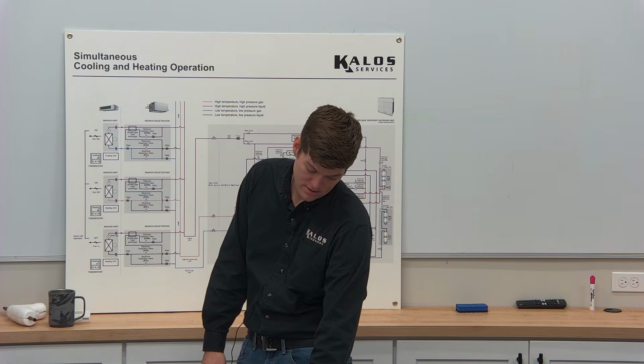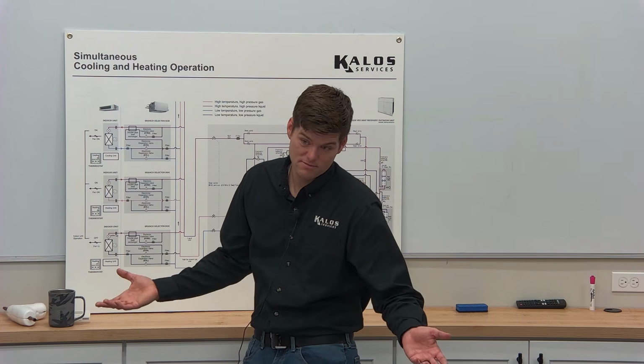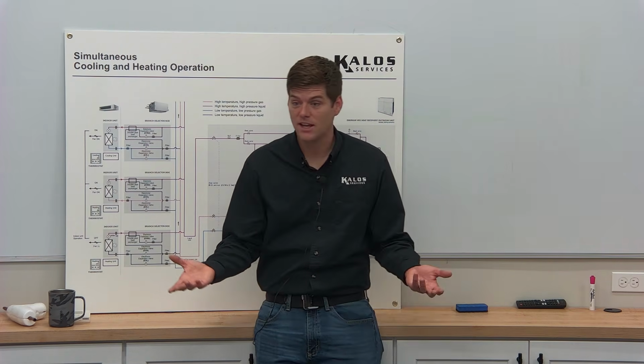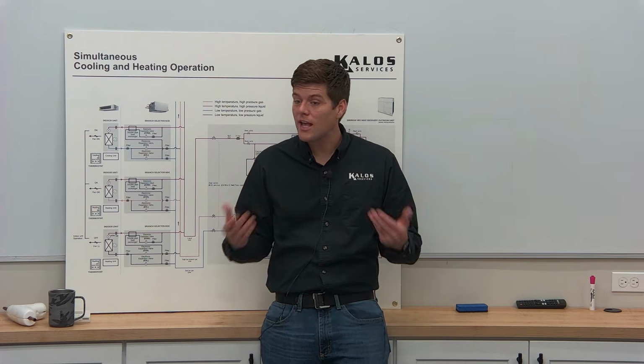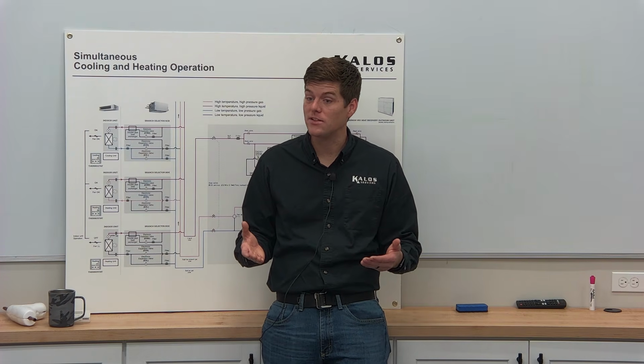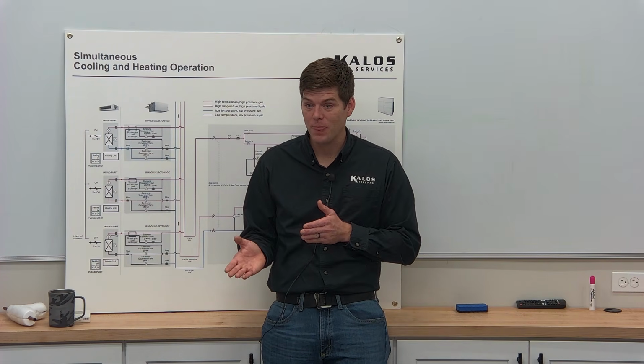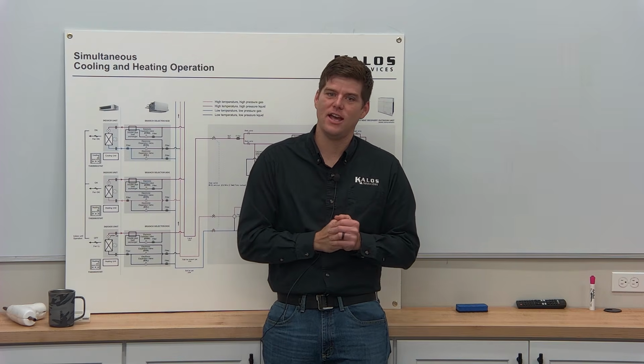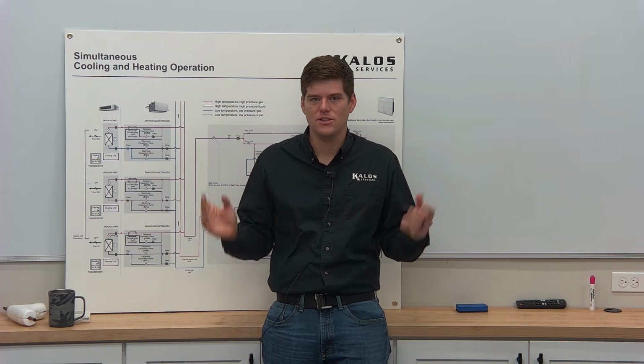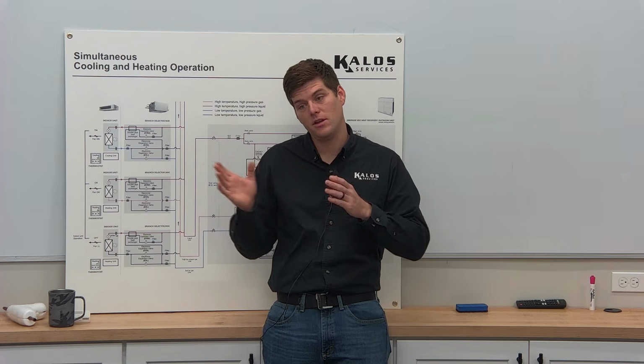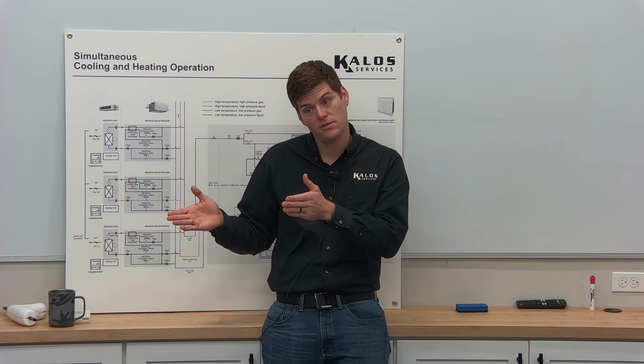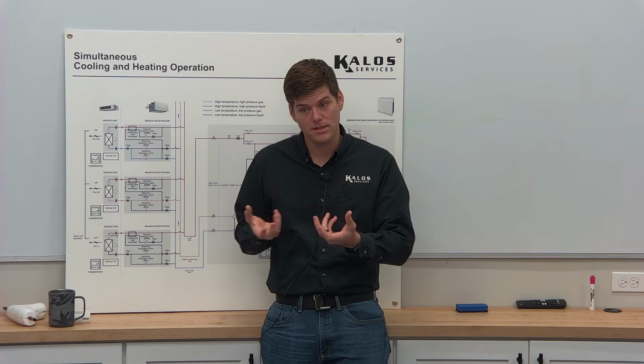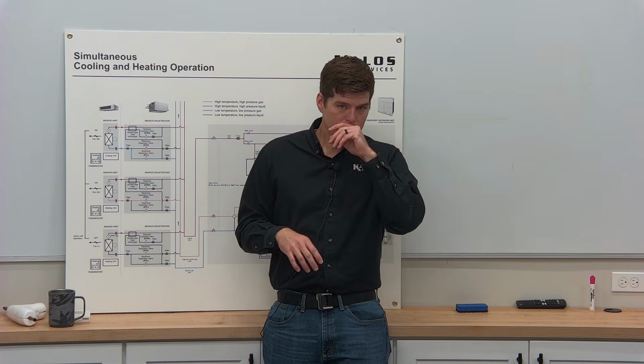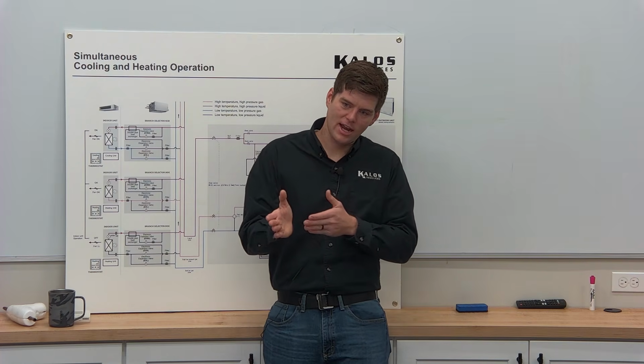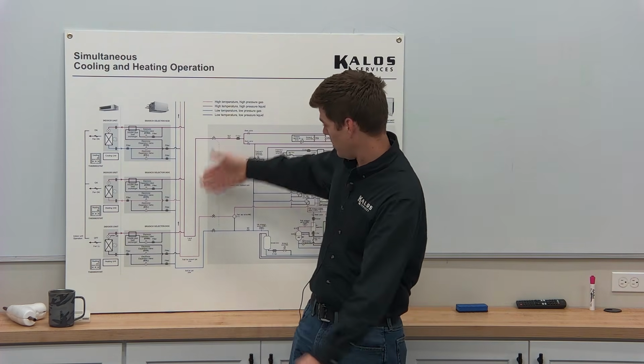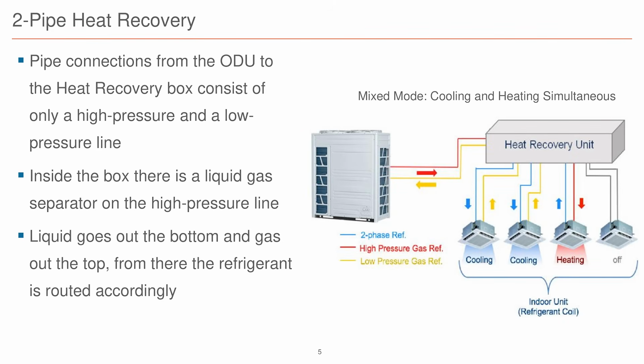So it's essentially a discharge line that's running out there? That's it. Yeah. It's just hot gas, dedicated hot gas. And we call it a dual gas line in the world of VRF because it could be either or. Same like a heat pump, so it's suction line or discharge line. Correct, yes. It's hot gas, that's it. So depending upon the mode, it'll determine whether it should be dedicated suction, have 2 suction lines, right? More flow, more refrigerant coming back to the outdoor unit, less restrictions, less work on the compressor, or it's dedicated hot gas, sending hot gas to one of these indoor units that's calling for heat, right? This is 2-pipe heat recovery.